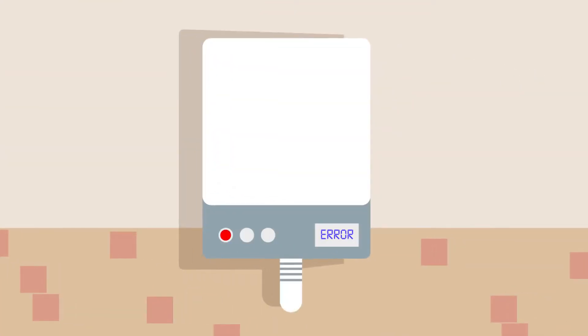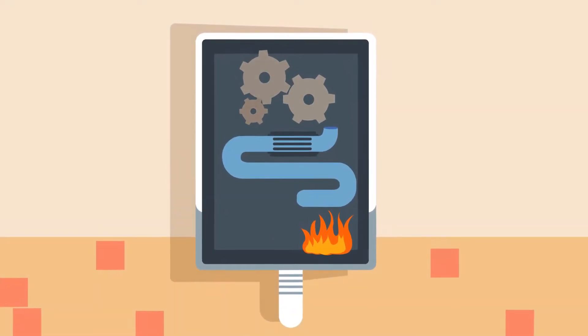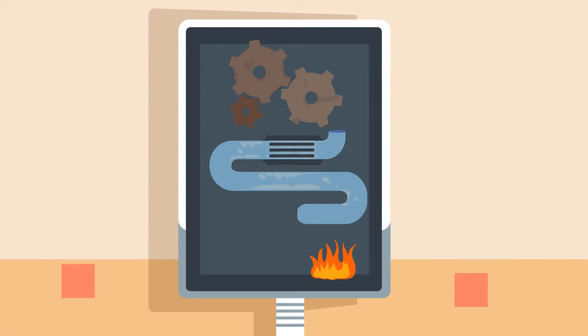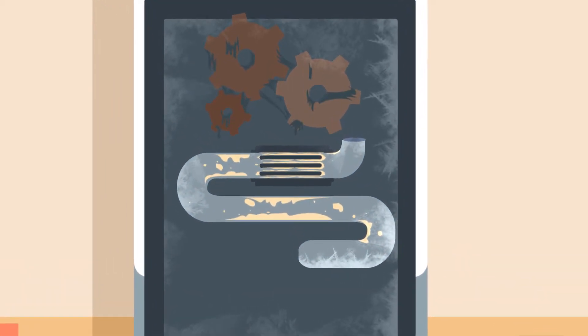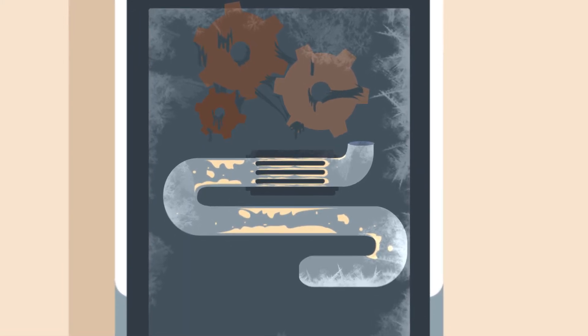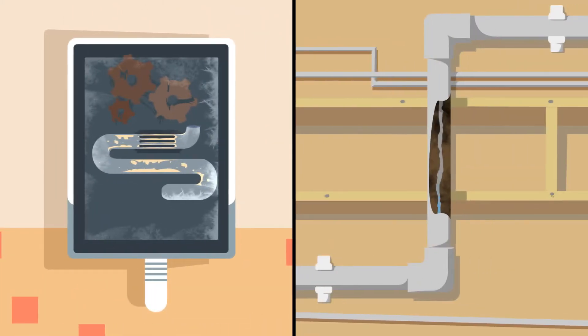But what has made your boiler conk out? Dirty water and sludge from scale and rust buildup in your heating system causes serious damage by clogging up the boiler's tiny waterways, damaging the pump and heat exchanger, ultimately resulting in boiler breakdown. Sludge also typically collects in the pipework and at the bottom of radiators, causing cold spots and clanging noises as the system fires up. Overall, a dirty sluggish heating system eats up more gas and costs even more money to run.